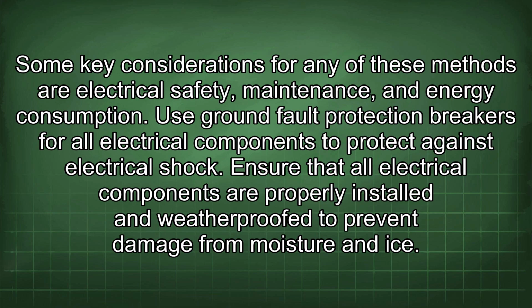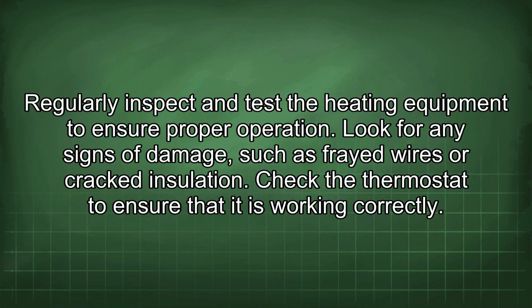Some key considerations for any of these methods are electrical safety, maintenance, and energy consumption. Use ground fault protection breakers for all electrical components to protect against electrical shock. Ensure that all electrical components are properly installed and weatherproof to prevent damage from moisture and ice. Regularly inspect and test the heating equipment to ensure proper operation. Look for any signs of damage, such as frayed wires or cracked insulation. Check the thermostat to ensure that it is working correctly.